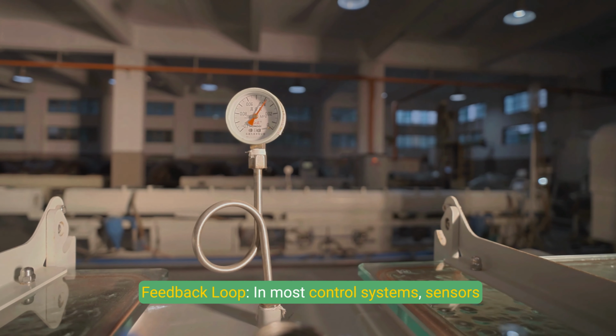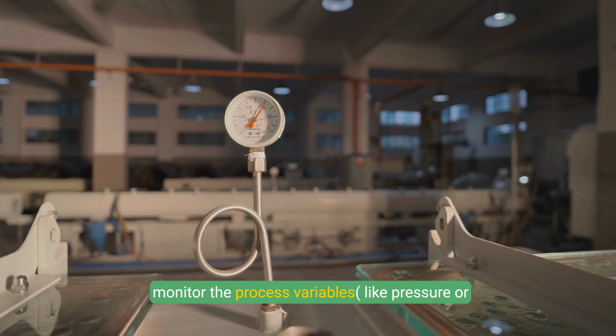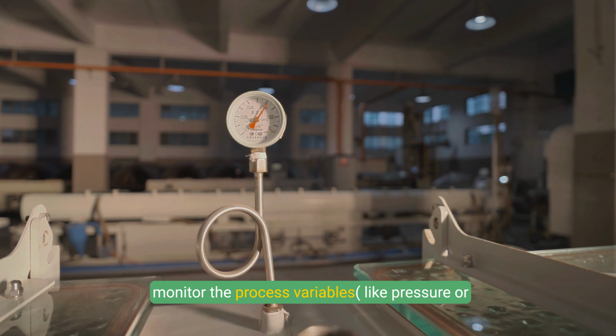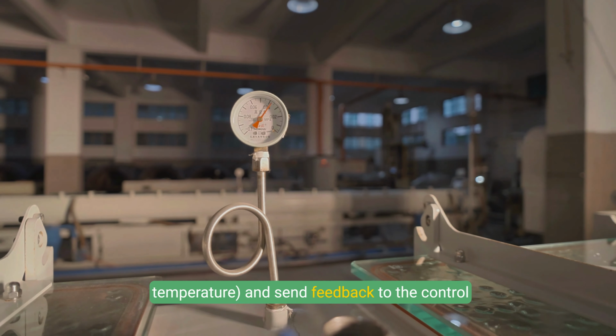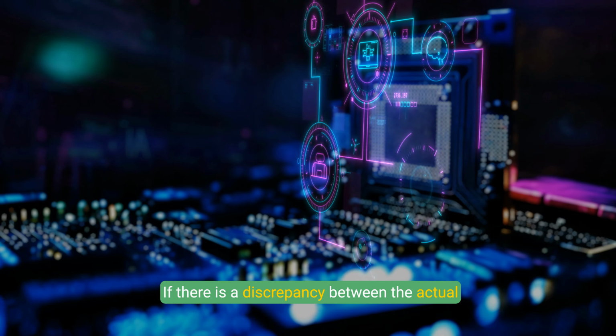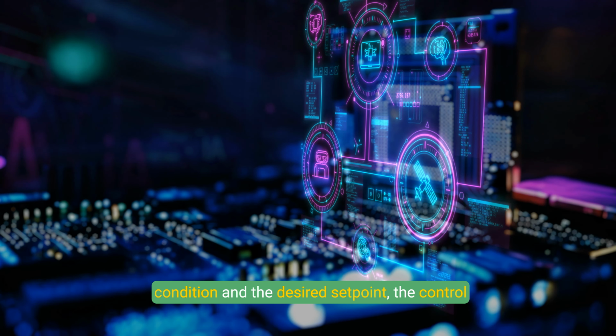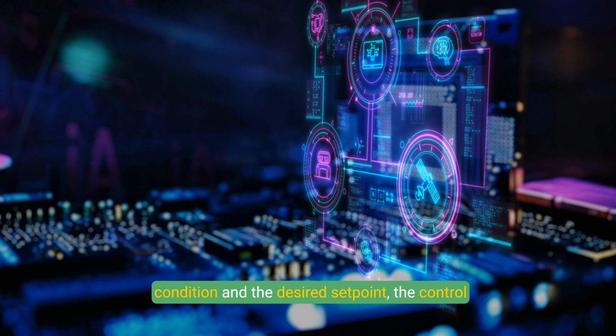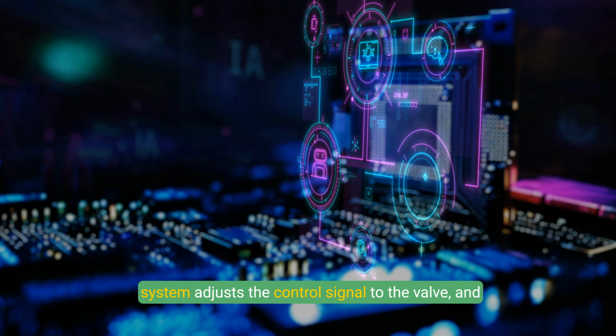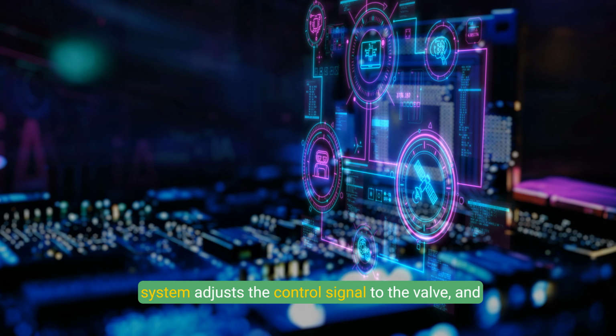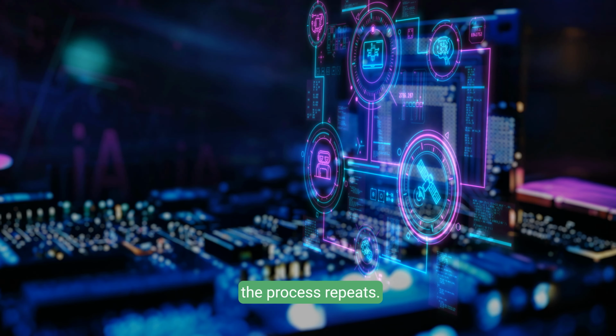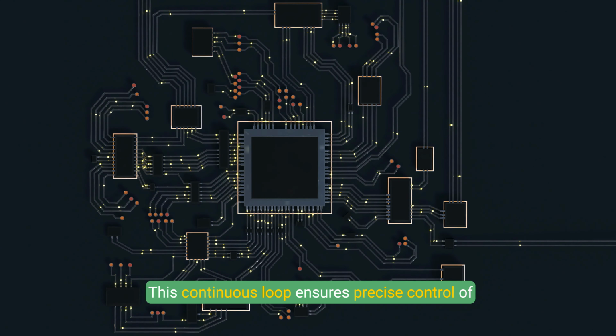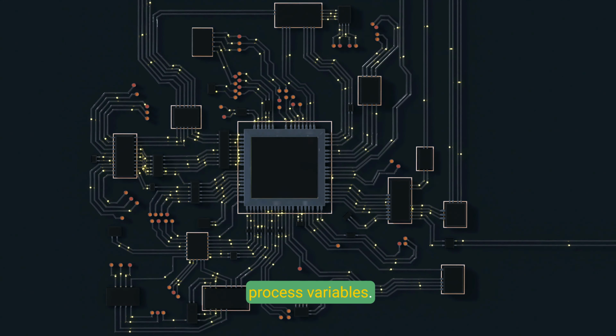Feedback loop. In most control systems, sensors monitor the process variables, like pressure or temperature, and send feedback to the control system. If there is a discrepancy between the actual condition and the desired set point, the control system adjusts the control signal to the valve, and the process repeats. This continuous loop ensures precise control of process variables.